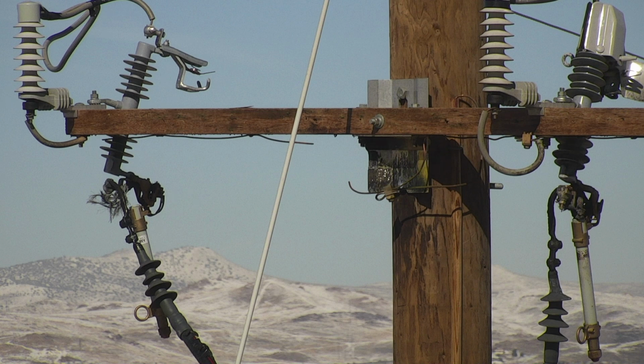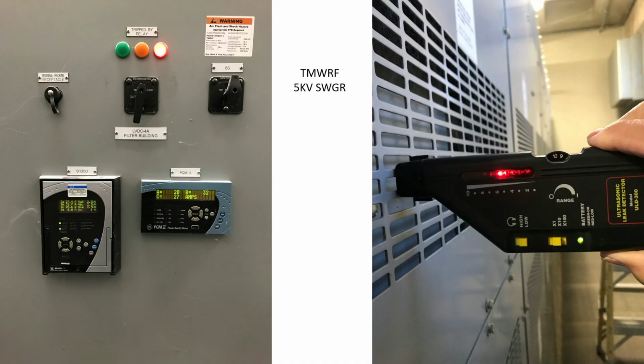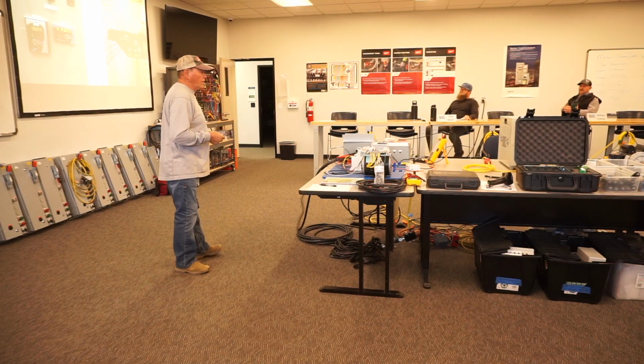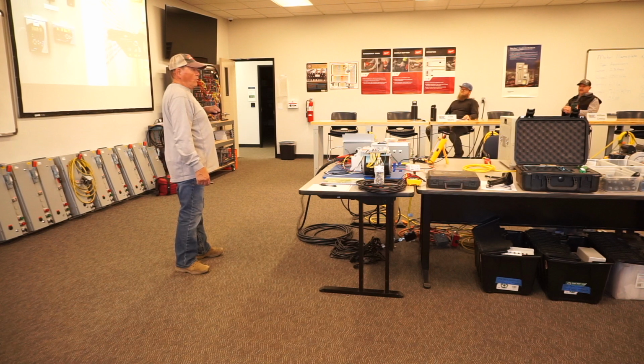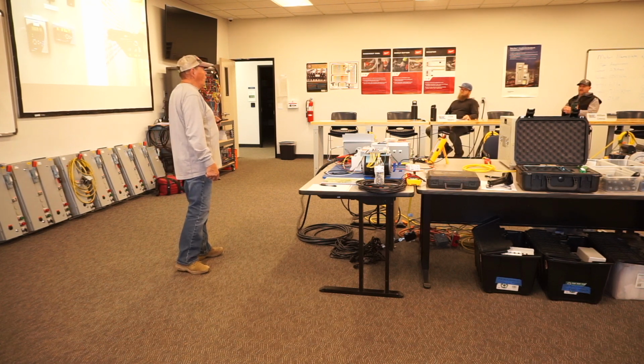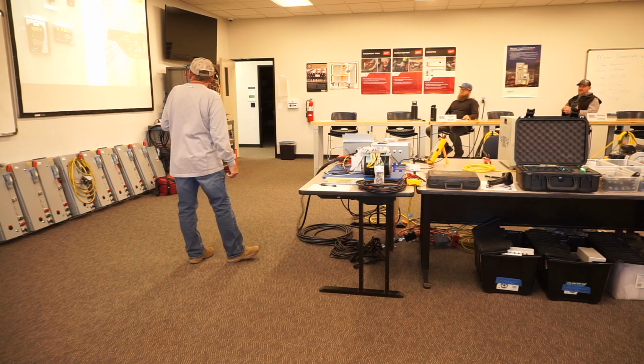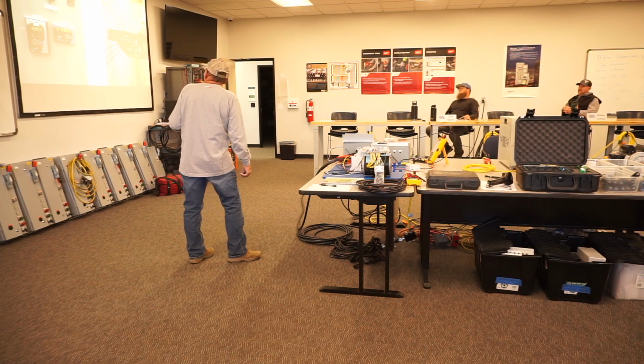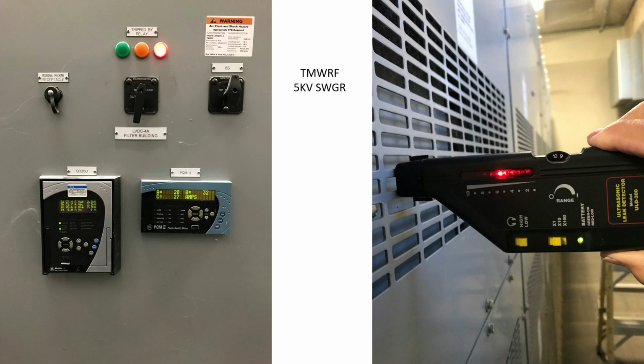That'd be a very rainy day, so the pole got pretty wet. So it provided enough conductivity that it just blew this, went to ground right here, and it blew the whole thing apart. I mean, it blew everything apart. But I flew my drone around that pole with all these images, and the power company realized it was their fault because they didn't have that ground wire grounded next to that arc flash guy.